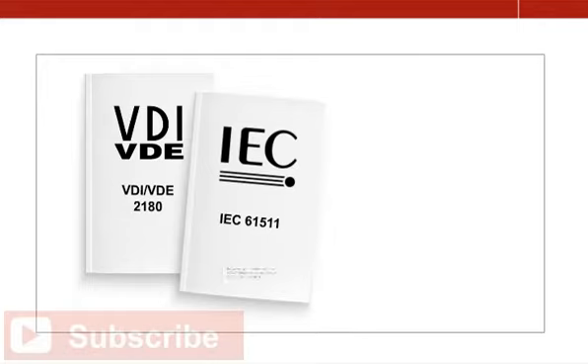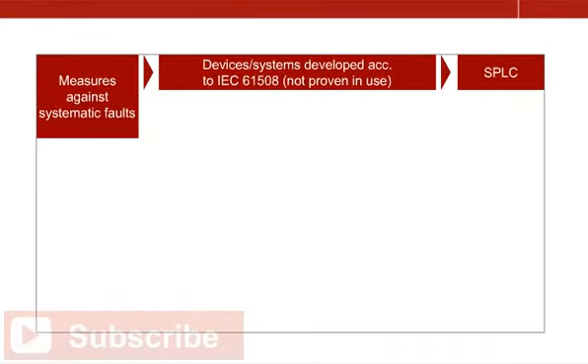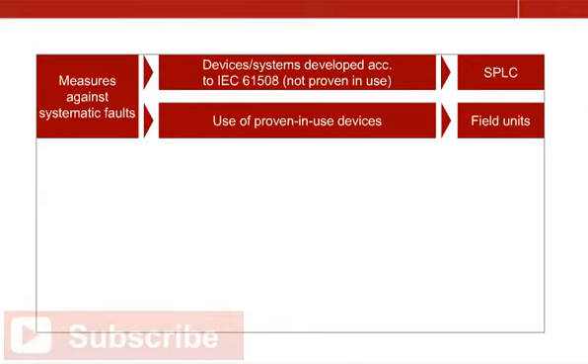According to VDI VDE 2180 and IEC 61511, measures against systematic and random faults, as well as measures related to fault tolerance, are required for devices used in safety instrumented functions. To exclude systematic faults with an adequately high degree of safety, it suffices to develop and manufacture electronic devices and systems not used in the field, such as programmable logic controllers, in accordance with IEC 61508. For field units, however, systematic faults can only be excluded by providing evidence of prior use.